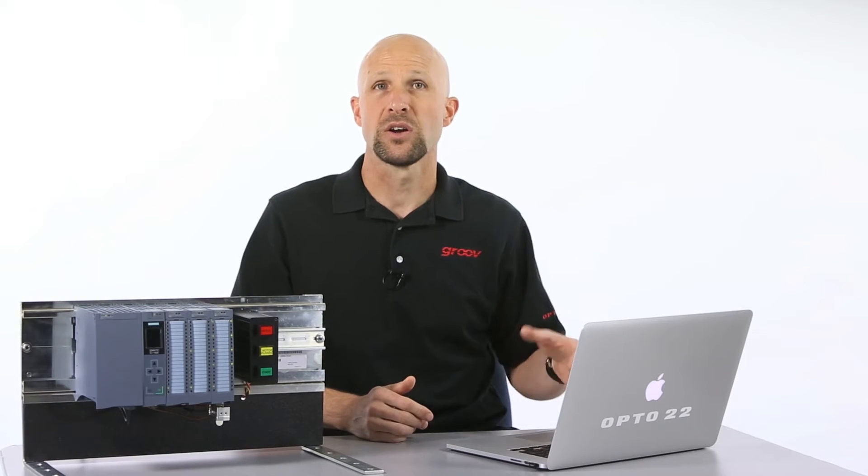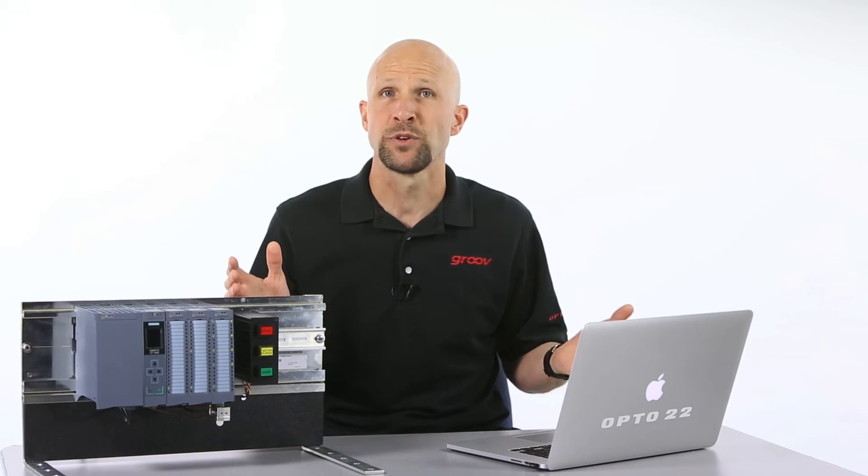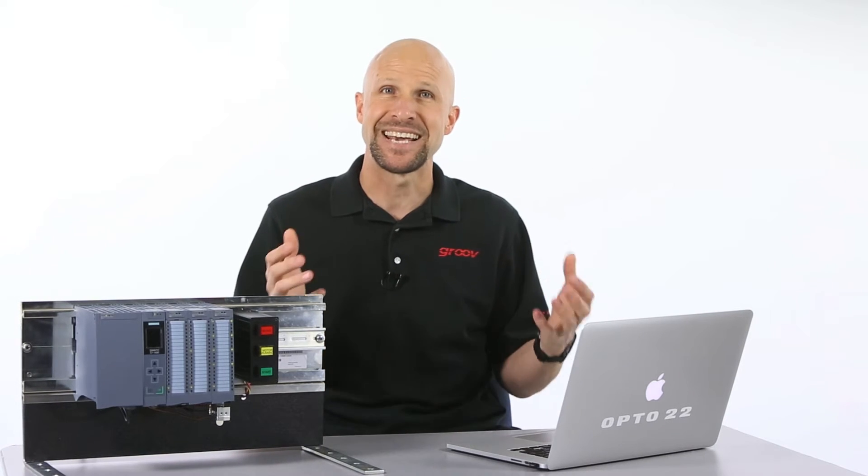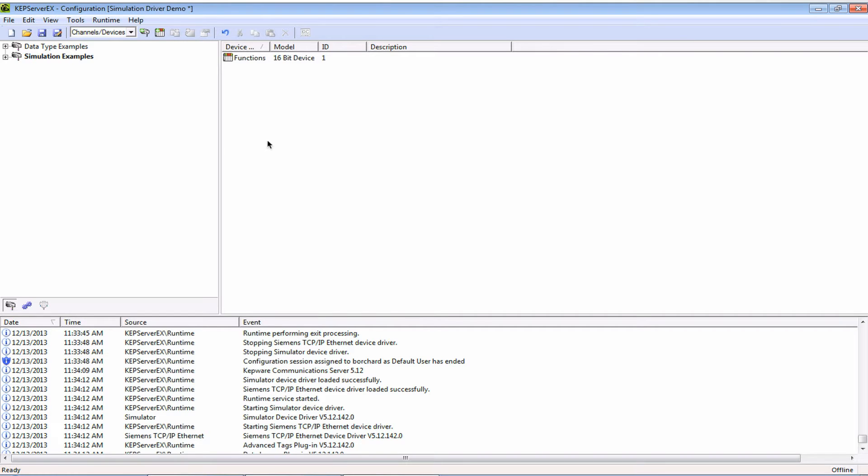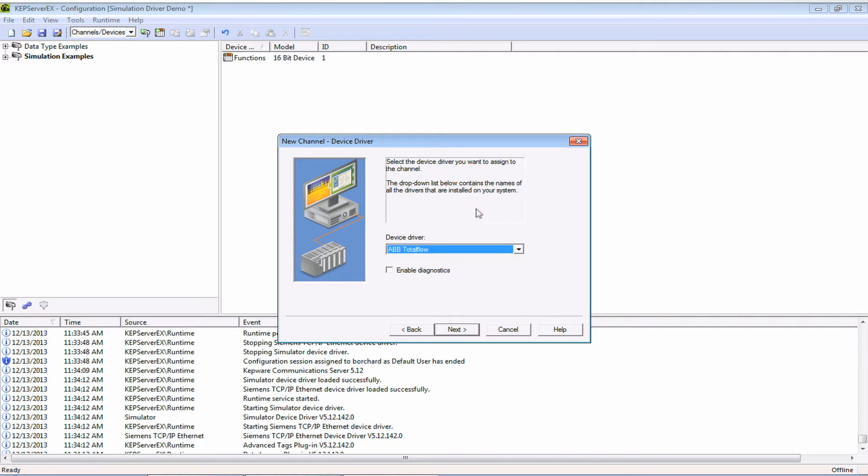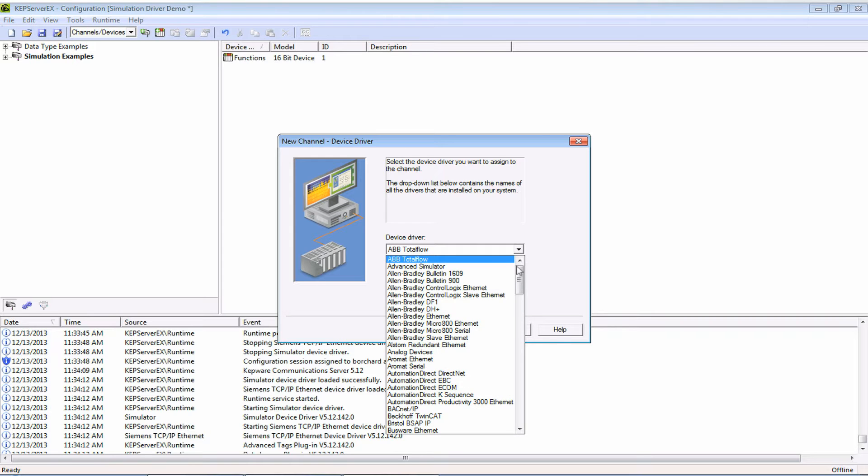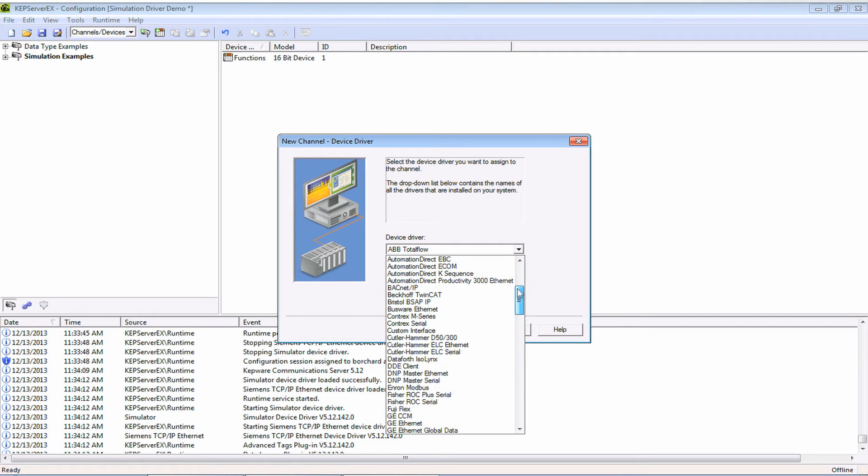I'm going to remote desktop to a Windows 7 PC. I've already downloaded and installed Kepware's KEPServer EX free trial that'll run with all features and drivers for a full two hours just like groov Server for Windows. So this means that together it's the perfect way to trial all the steps in this video for free. Let's go ahead and open up KEPServer's configurator and click new channel. Give it a name, I'm going to call it Siemens, and from the drop-down driver list I'll choose Siemens TCP IP Ethernet.